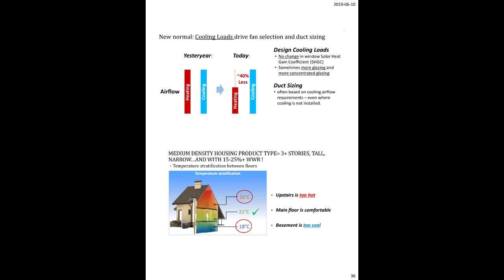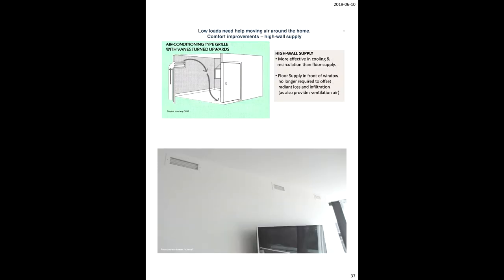Traditional duct systems are designed on what's called displacement. In other words, the air pushes into the room through a register and displaces the air out through the return air. That's what it was designed as. What we have to move towards is this thing called heating and cooling and conditioning by diffusion. In other words, we need to start to mix the air. In the residential world, we don't even know what it means to look at a register and talk about throw. In the commercial world, this is very important because you need to mix the temperatures in the room without affecting the homeowner.